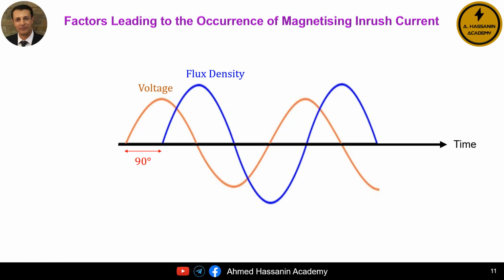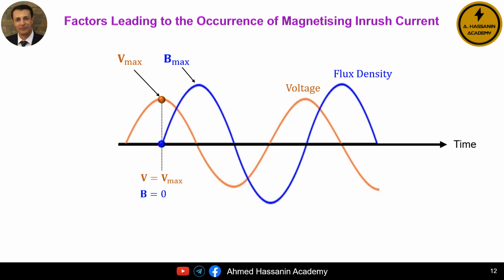Accordingly, when the transformer is disconnected, the iron core retains a certain amount of magnetism or magnetic flux density, which we refer to as the residual magnetism in the transformer core. This residual magnetism may be positive, negative, or 0, depending entirely on the exact moment the transformer was disconnected from the network. For example, as clearly shown here, it is possible to energize the transformer when the voltage value is at its maximum positive value and the magnetic flux density is 0, meaning there is no residual magnetism in the iron core. Or the transformer can be energized when the voltage value is 0, but there is residual magnetism at its maximum positive value. Or, for example, the transformer can be energized when the voltage value is 0 and there is residual magnetism at its maximum negative value, and so on.